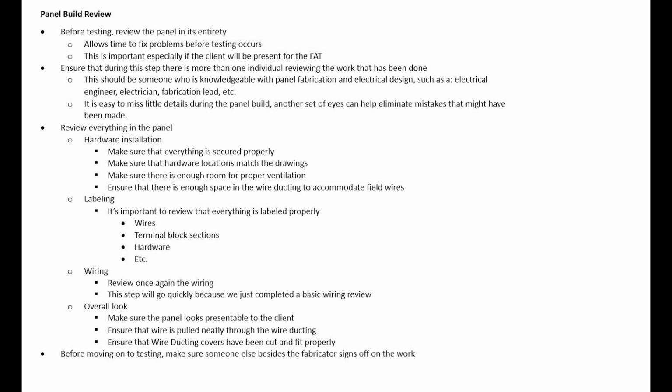So again, making sure it's secure and it's in the right location. We want to make sure that there's enough room for proper ventilation for all of our hardware. That includes making sure that the hardware is not too close to wire ducting or other hardware that needs a specific amount of spacing for heat dissipation. So double check all of these things.